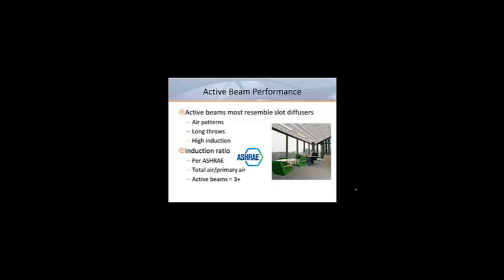According to ASHRAE, the induction ratio of any air outlet is equal to the total supply air volume divided by the primary air volume. So if an active beam was supplied with 500 CFM of primary air, but the total supply air in the discharge jet was 1,000 CFM, it would have an induction ratio of 2. The good news is that many active beams available today have induction ratios of 3, and this is likely to rise through further innovations in nozzle or outlet design.